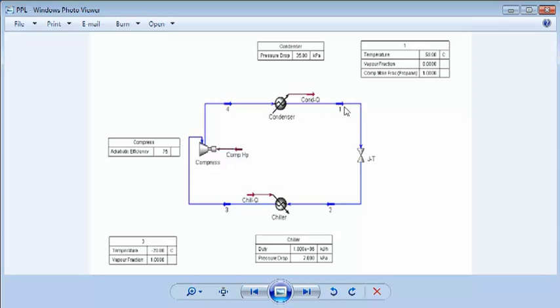Stream 1 enters at a temperature of 50 degrees Celsius and passes through a JT valve. The JT valve in this operation serves as an optimization tool, which we are able to use to reduce considerably the duty of the chiller here, that would have been required to effect the proposed temperature drop. We need to meet up with a given dew point specification at stream 3. The analysis of the JT valve will seem much clearer when we complete our simulation case.